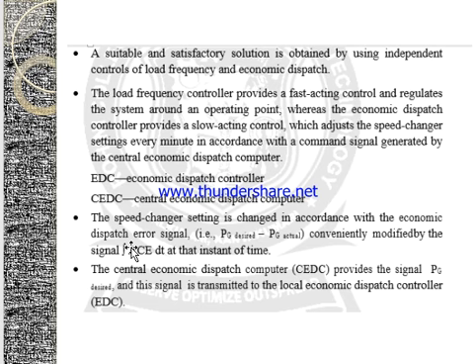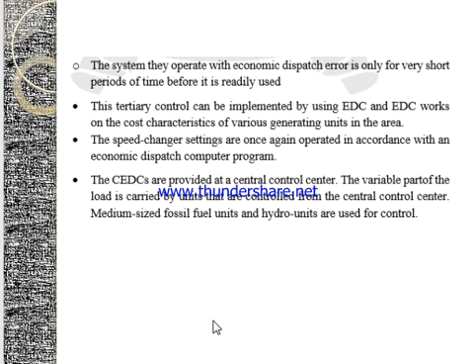While considering the speed change settings, when changed in accordance with the economic dispatch controller, it is modified by the signal ACE — specifically the integral ACE — at that instant of time. The CEDC provides the signal and this signal is transmitted to the local EDC. The system which operates with the economic dispatch error does so for only a very short period of time before it is readily resolved. This tertiary control can be implemented using EDC, which focuses on the cost characteristics of the generating units, and the speed change settings are operated in accordance with an economic dispatch computer program.